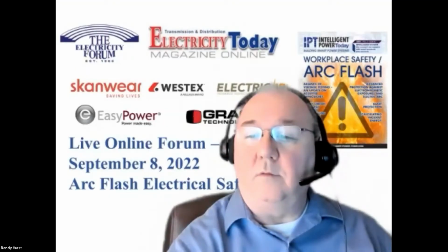A lot of the time it will depend on how the fabrics react in an Arc Flash situation when the arc is increased. Imagine you have a 10 cal fabric and you put another 10 cal fabric behind it. The fabric at the front has only withstood a 10 cal arc in its first test. If you wanted to increase the arc flash to 20 cal, that first fabric is almost going to disappear in the arc flash. So you've got to make sure that the 10 cal fabric behind it still has enough protection left after the first layer has disappeared. So there's not a straight down the middle answer, I'm afraid. It has to be done per garment, per fabric. That's right. Okay, great.